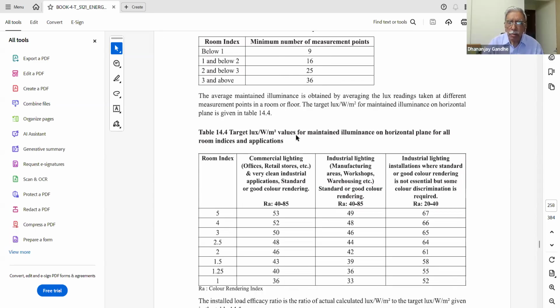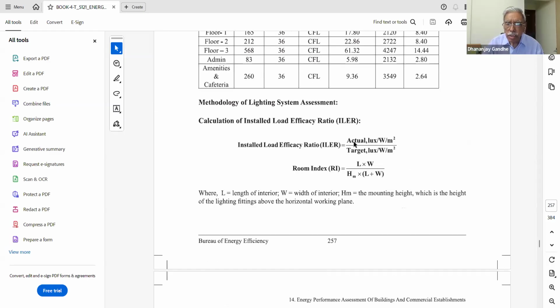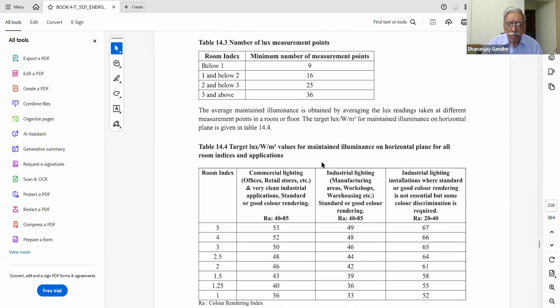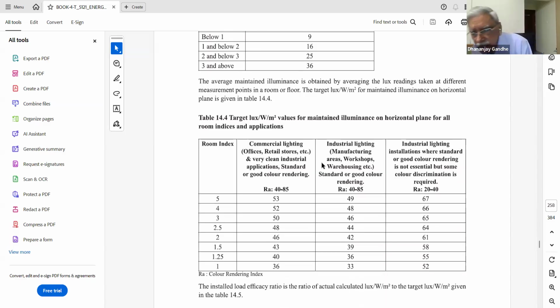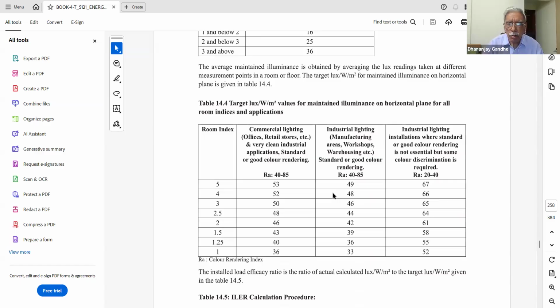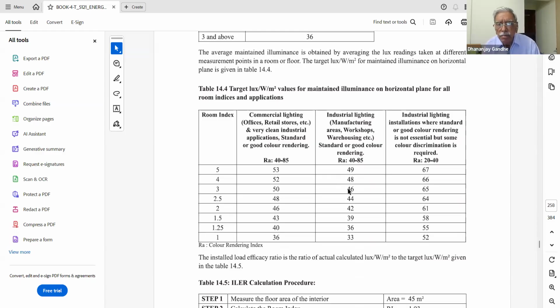So room index figures are given there, and you work out this ILER using the actual lux value and the target value for that particular area. These target lux values are specified by standards. For different types of areas, they are mentioned in the standard books, and this particular book also mentions that. The target lux per watt per m square gives you the indication of the illuminance. Actual lux is the actual illuminance maintained, and target lux is what is designed for that particular area.